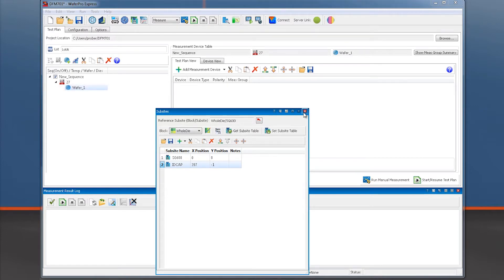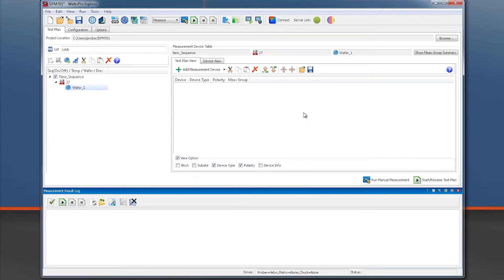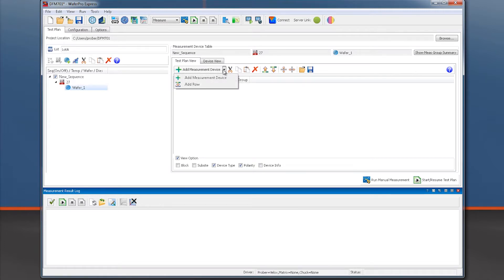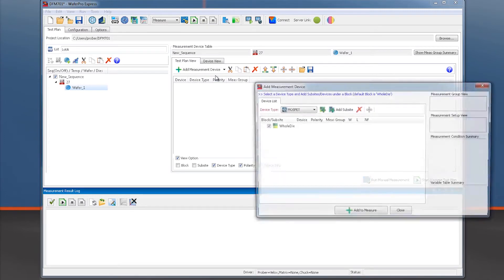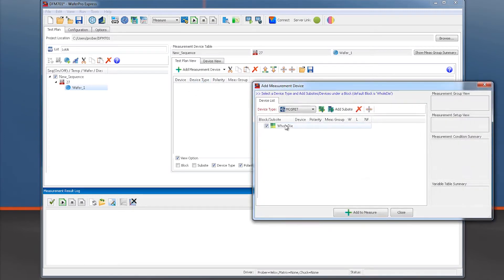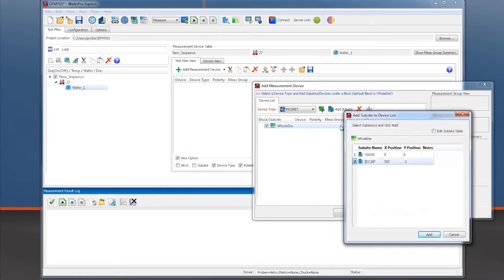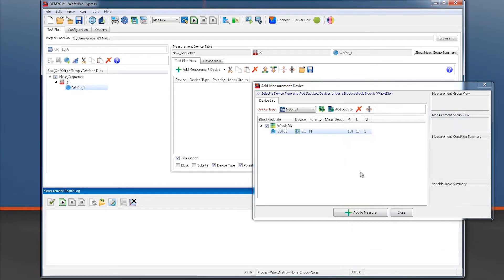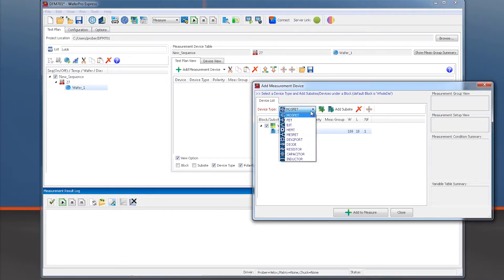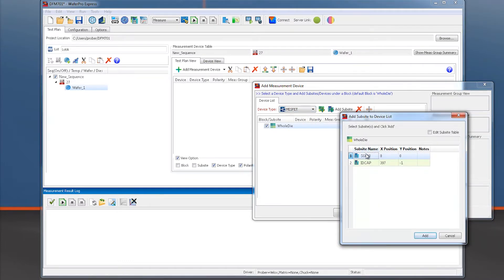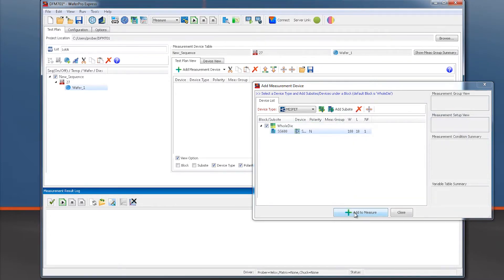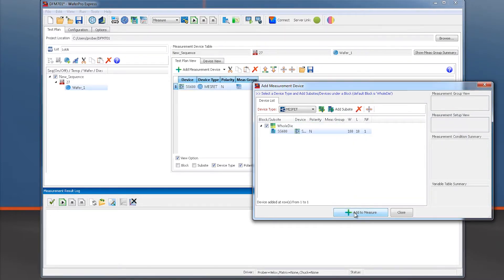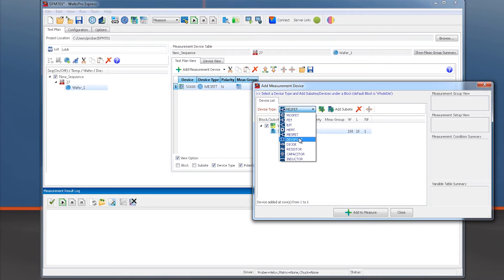Next we want to add these subsites to our measurement table, so we click on Add Measurement Device, select the whole die, and then add a subsite. Now we select the device SG600 and add it to our list of devices within the reticle. We specify this device to be a MESFET based on the pull down list. After we click Add to Measure, our device gets added to the measurement table.